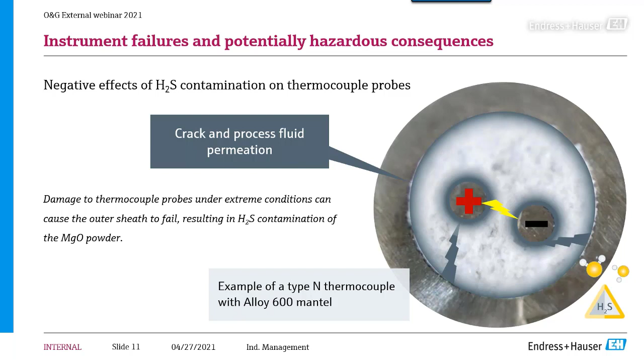When this short circuit takes over the initial hot junction of the thermocouple, which is supposed to be at the end, the thermocouple starts measuring quite well again, but unfortunately in a completely different location. And there is no way to recognize this from the control room.